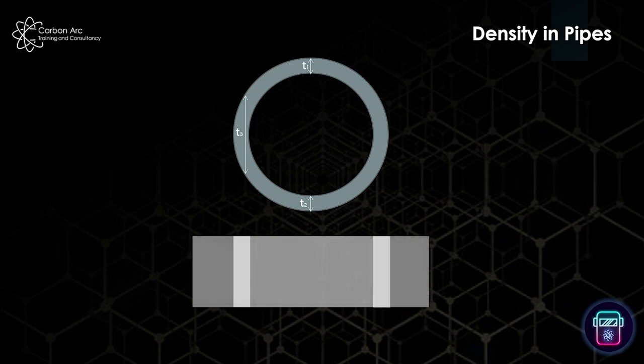Well, what's going to happen is we're going to see something like this. To the far extremes of the image where there is no pipe, that'll be fairly dark, if not pitch black, because all the radiation will be going through there. And then as we come in towards the center, we'll see the very large penetrated thickness of that T3 position, and that won't let too much radiation through. And then we'll see a gradiented sort of center portion, as of course as we move through to the center line, the combined thickness becomes thinner and thinner. So what a densitometer does is looks to read those differences in density.